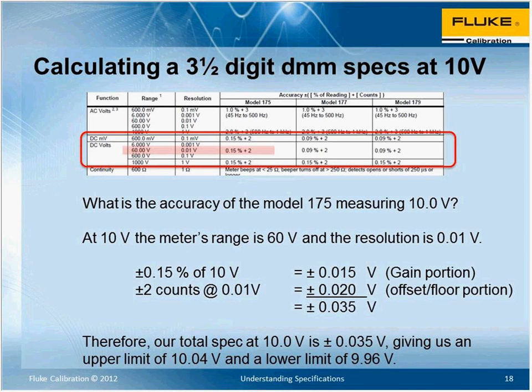So this is an example of a 3.5-digit DMM spec, and I may go through this in the next webinar in detail, but if you were trying to determine the accuracy of the 10 volts on a Model 175 DMM, you would first look at the range, the 60 volts you're on, the resolution, and then the spec. So we talked about the gain and the floor. If you put those together, you basically get a 0.035 volt error allowance. And if you put that back into your 10 volts, it will tell you that you have an upper limit of 10.04 or 9.96, depending on your rounding practices. But I just wanted to bring that up in case you weren't familiar with specifications and looking at these multi-product calibrators, to give you an idea of how to interpret those specifications.